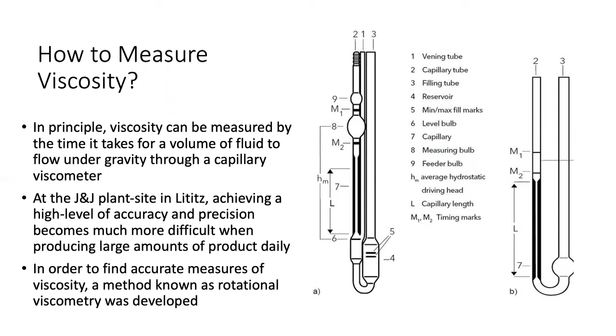So, finding viscosity using rotational viscometry. Product is run through a cup containing a spindle, and the amount this spindle rotates generates a value for torque. Looking at the equation below, coefficients can be used to determine a value for apparent viscosity. These coefficients depend on things like the approximate viscosity range of a substance and the type of spindle being used.